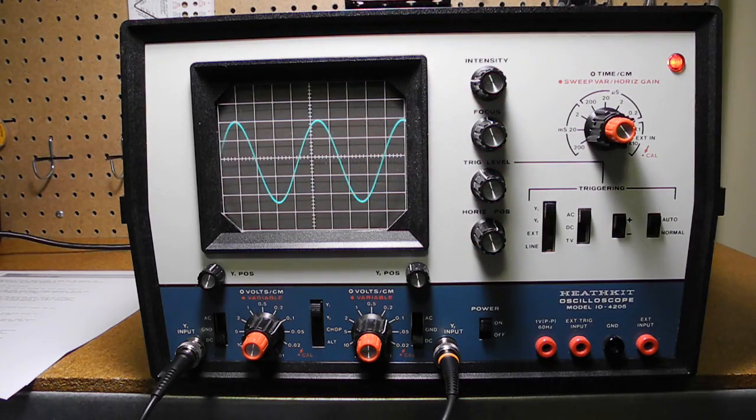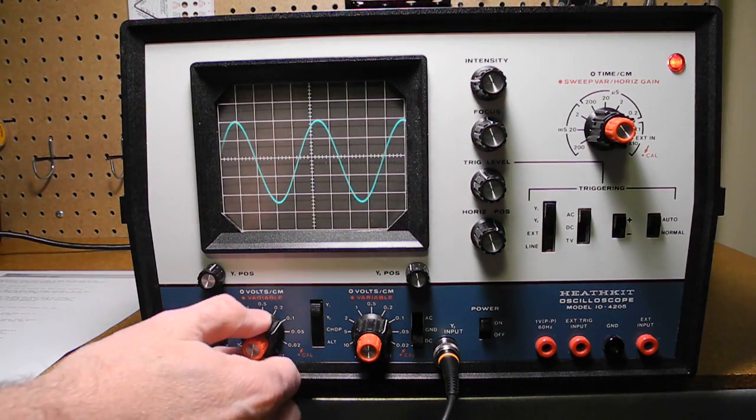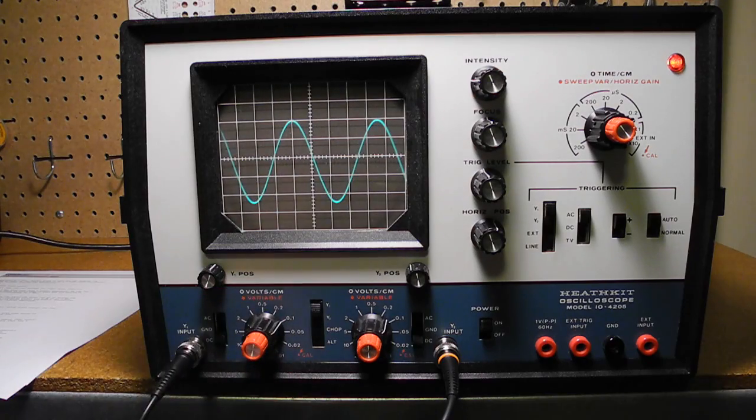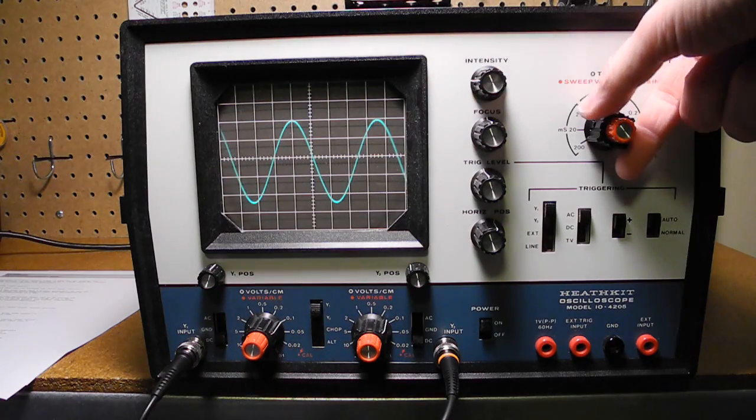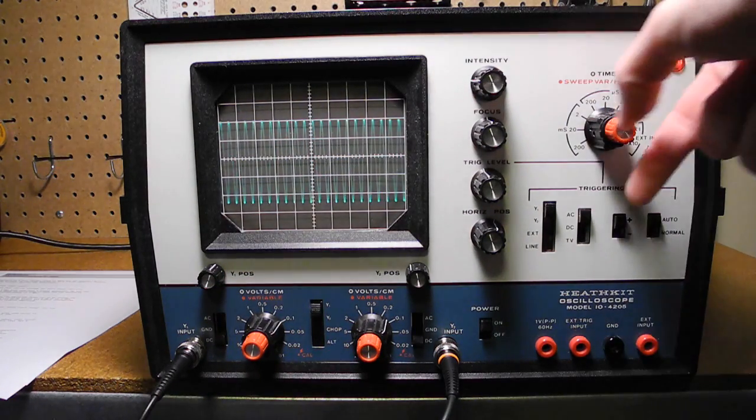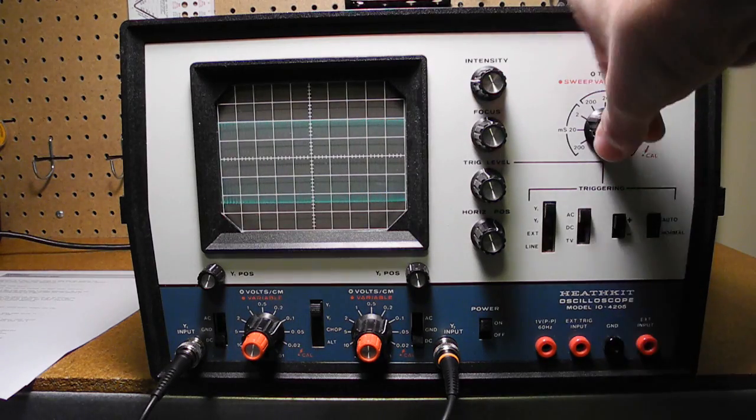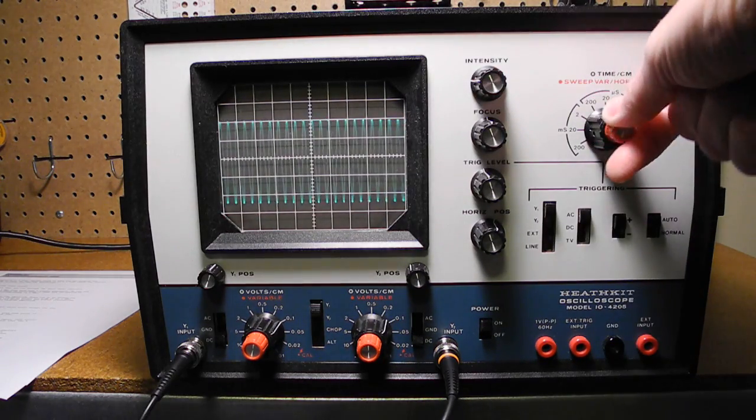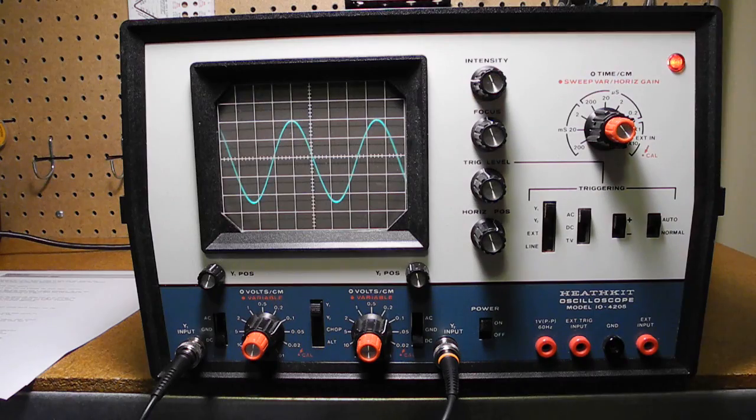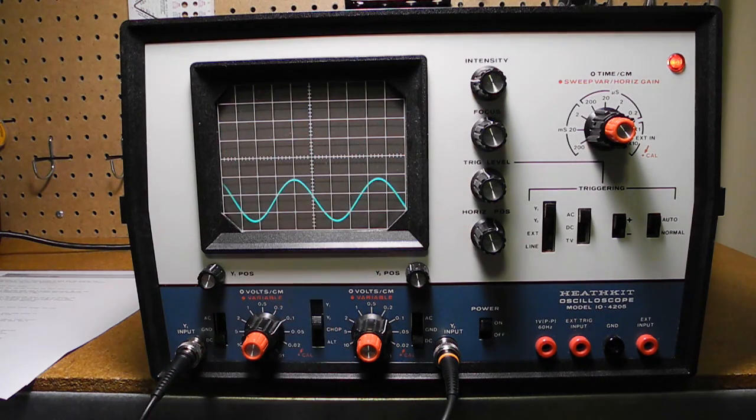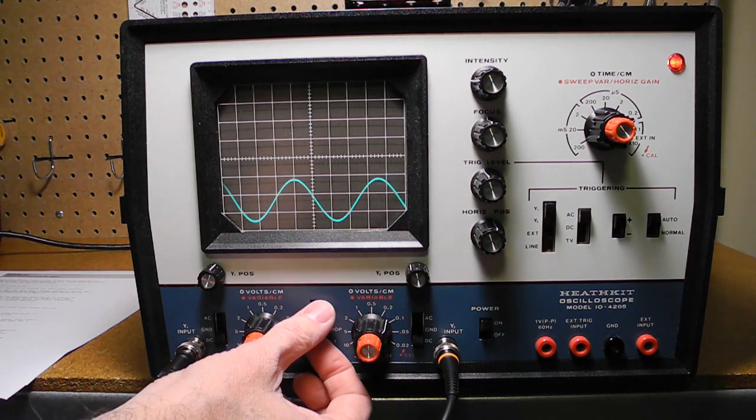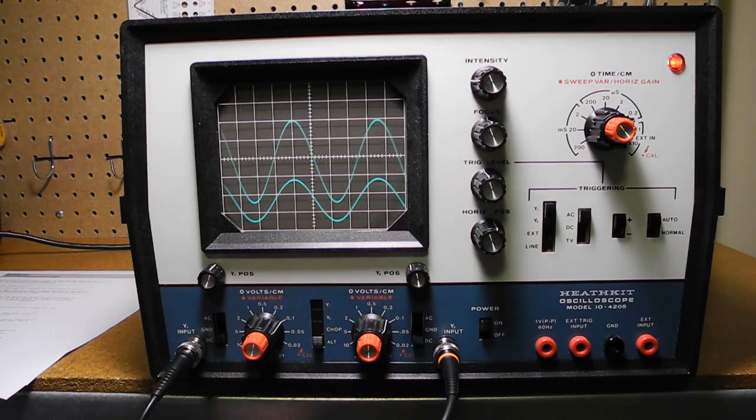Now I'm looking here at channel 1. We can adjust the volts per centimeter if desired. We can also change the sweep rate to something lower and adjust it here if we take it out of the calibrated position. I can also switch to channel 2, which is also showing the same input, or we can switch to the alternate mode where it alternates and we can see both traces.